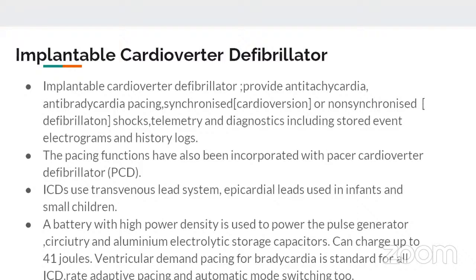ICDs use transvenous lead systems for pacing and shock, whereas epicardial leads are used in infants and small children. It consists of a battery with high power density, which is used to power the pulse generator, the circuitry, and the aluminum electrolytic storage capacitors. It can charge up to 41 joules. Ventricular demand pacing for bradycardia is a standard feature for all ICDs.